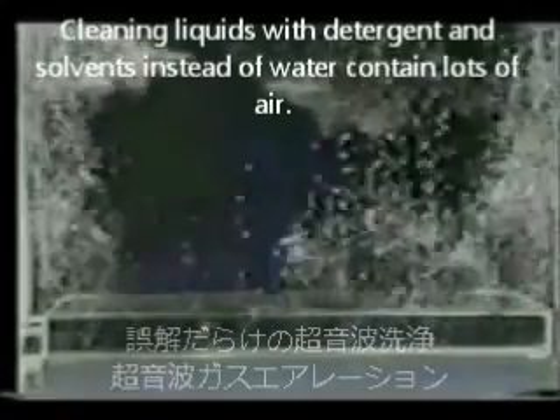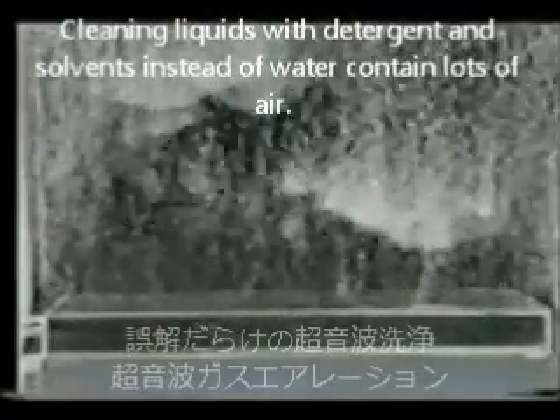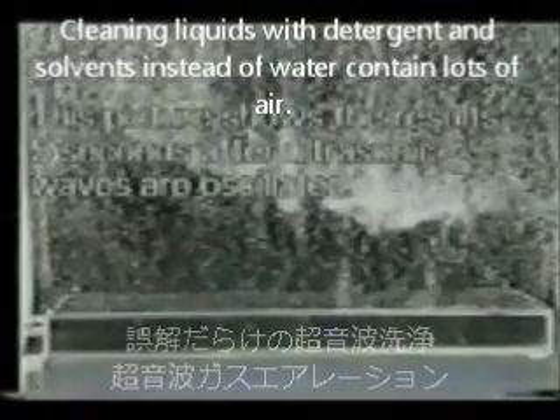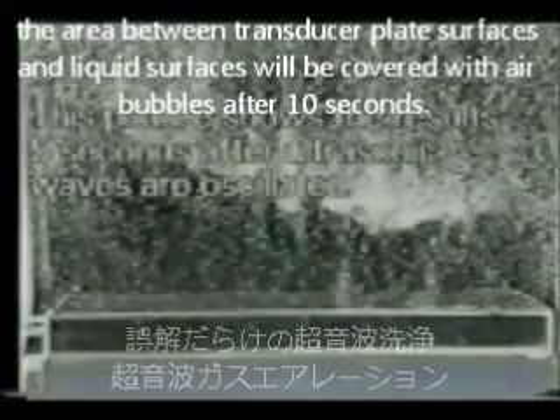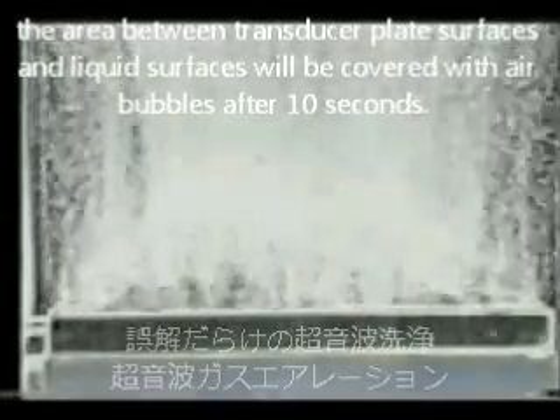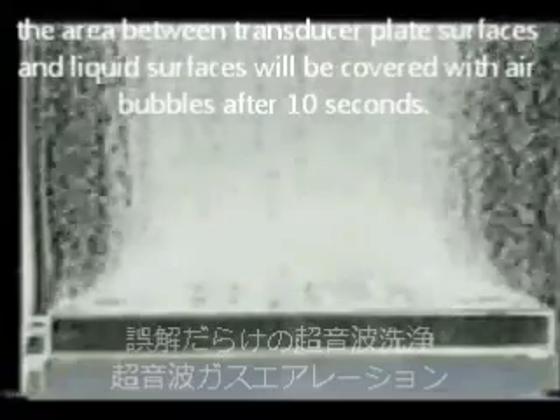Cleaning liquids with detergent and solvents instead of water contain lots of air. If you begin radiating ultrasonics without degasification, the area between the transducer plate surfaces and the liquid surfaces will be covered with air bubbles after 10 seconds. This is called the ultrasonic bursting phenomena, or ultrasonic gas aeration.